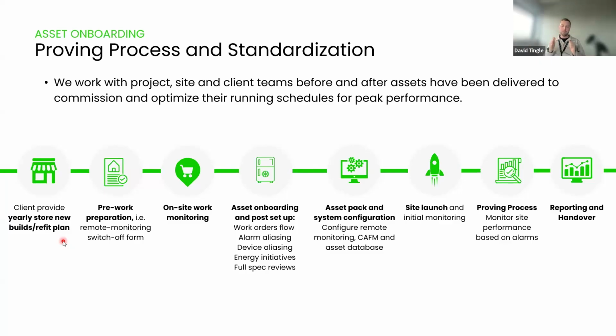So what we do is look for 4 consecutive weeks of zero alarms from that site, which sounds almost impossible, but that's exactly where we've got to. We've now put hundreds of sites through this process and delivered them to that line following these steps. It's worked really well to deliver a consistent, optimized site across an estate, and we've seen the knock-on effect too - reduced noise, reduced work orders to contractors - which all plays into a cost saving as well.